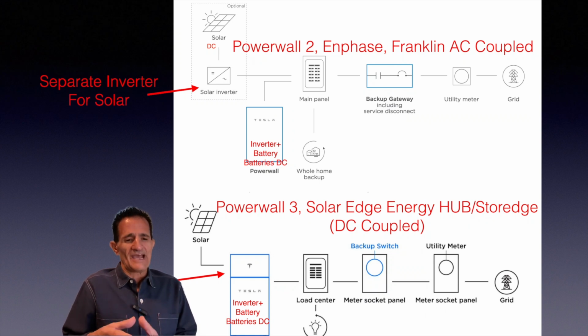Now, if we're adding a battery, like the Powerwall 2 or these other Enphase or Franklin systems, that battery actually has an inverter inside of it because batteries are also DC. So anytime the battery is charged, the AC electric has to be converted over to DC to charge that battery. That's built into these systems as a separate inverter. And when you're running on battery, that DC power must be converted over to AC so your home can use it. So in these three systems, that conversion happens inside the same box that has the battery.